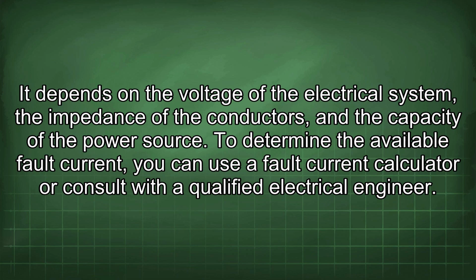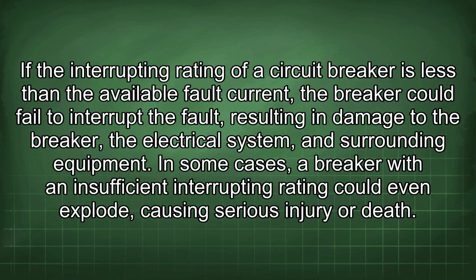power source. To determine the available fault current, you can use a fault current calculator or consult with a qualified electrical engineer. If the interrupting rating of a circuit breaker is less than the available fault current, the breaker could fail to interrupt the fault, resulting in damage to the breaker, the electrical system, and surrounding equipment.